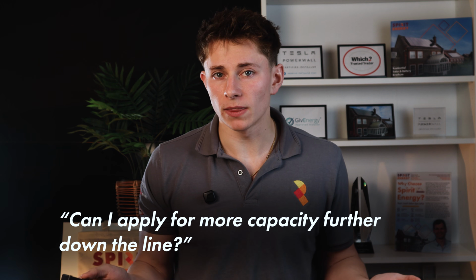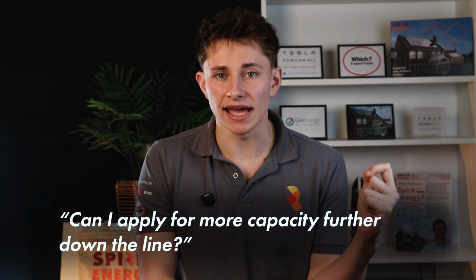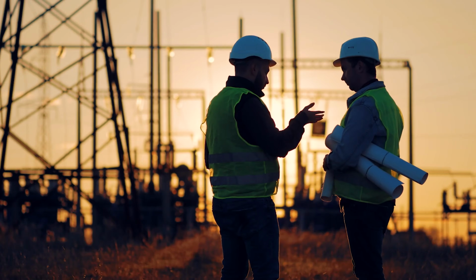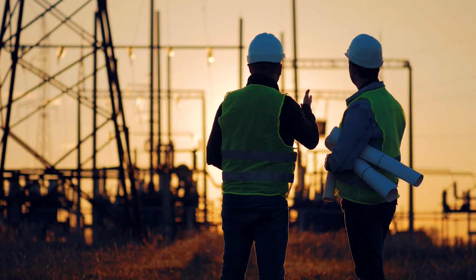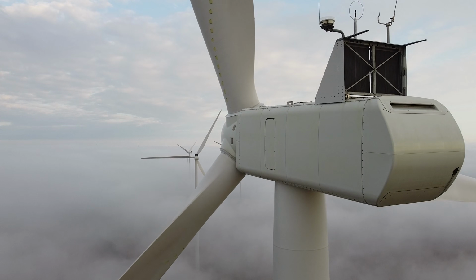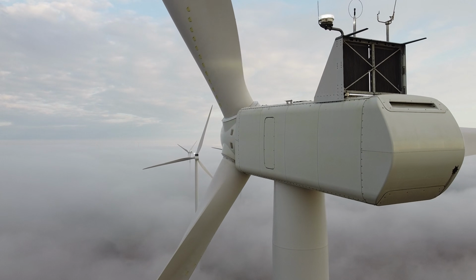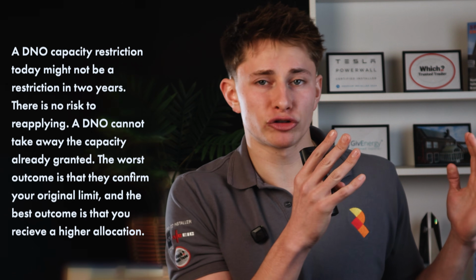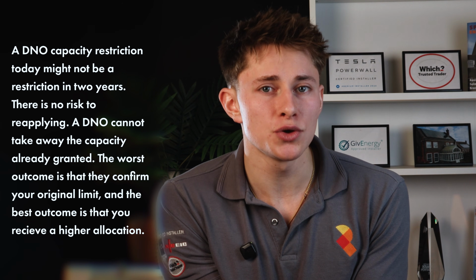Another thing we're asked is, can I apply for more capacity further down the line? And the answer to that is yes. If you're reapplying because you were originally restricted by the DNO, then you've probably been restricted because the local grid is not strong enough at that moment in time to support your requested capacity. However, the grid is constantly being upgraded. Substations are refurbished, cabling is replaced, and new capacity is added to support the country's electrification. This means that a capacity restriction today might not be the case in 2 years.